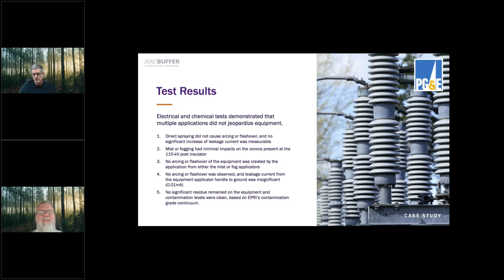So the misting and fogging had minimal impacts on the corona present at the 115 kilovolt post insulator. So that's important to point out, minimal impacts on the corona that's present. That's quite valuable information. Of course, no arcing or flashover was observed on the equipment from the application, from the mist or the fog. Leakage current from the equipment applicator handle to ground was insignificant. No significant residue remained on the equipment, and contamination levels were clean based on that finding.